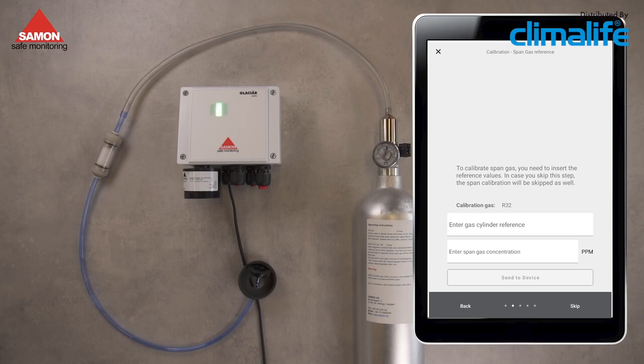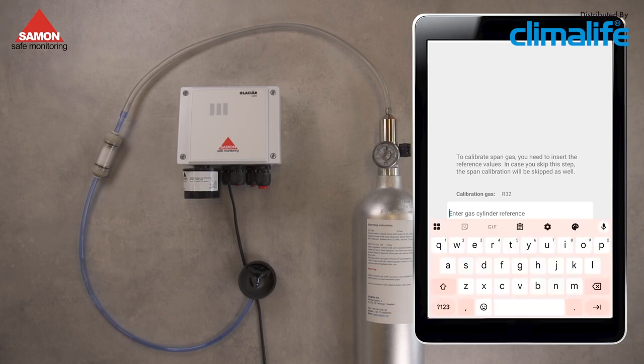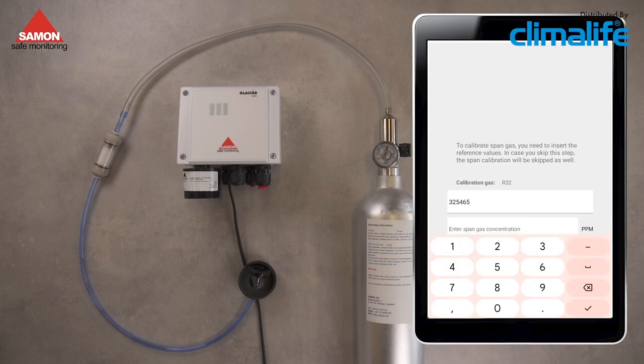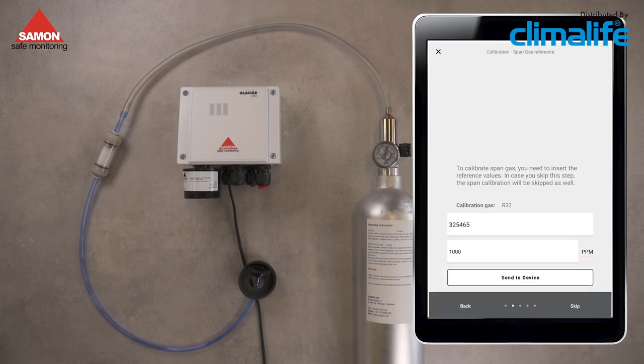Enter the gas cylinder reference, serial number of the reference gas or other relevant information to be shown on the certificate for traceability purposes. Enter the concentration of the gas used for calibration. Click Send to Device to set the gas concentration used for calibration.